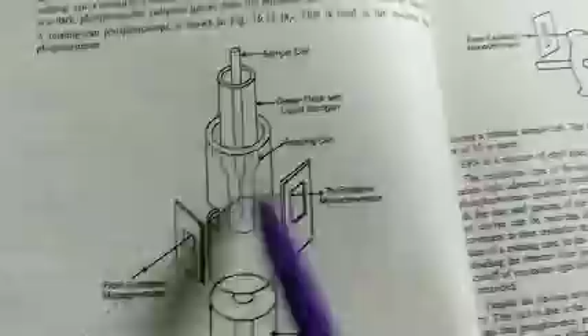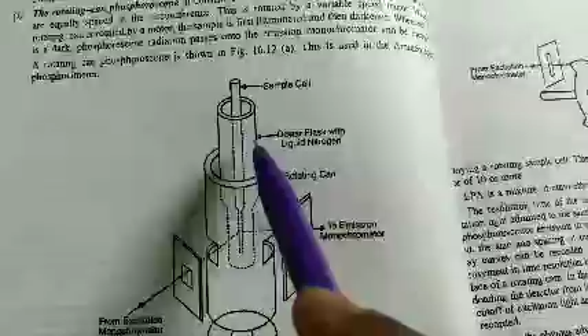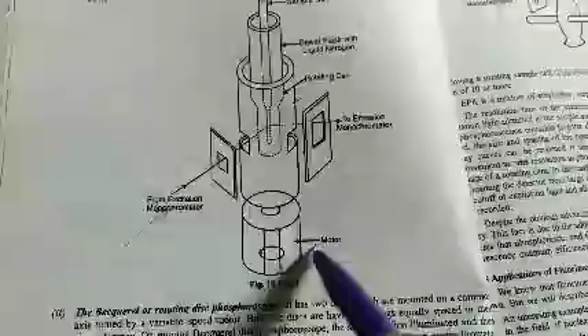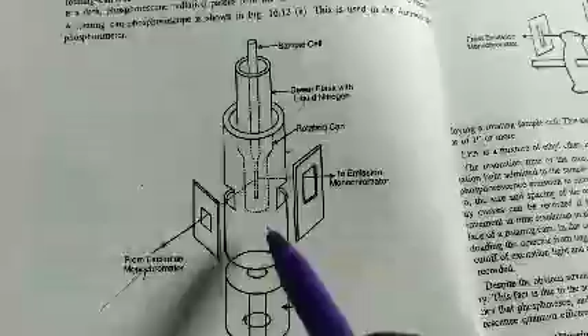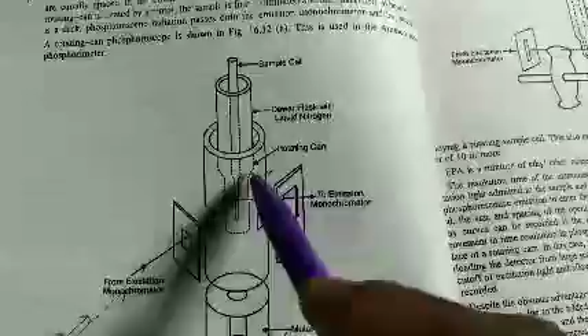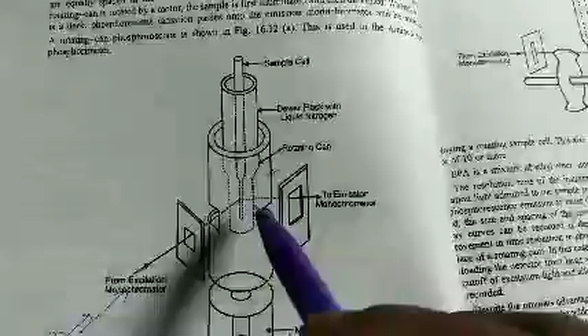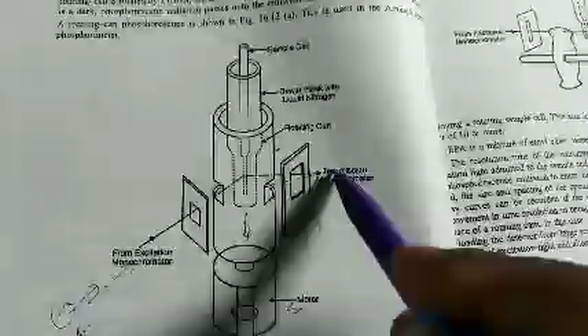In the rotating can phosphorimeter, the light source comes in, and the sample is kept in a Dewar flask. The Dewar flask is filled with liquid nitrogen, and this is the rotating can. The rotating can is attached to a motor, so there is an up and down movement. Here is the UV source of light, and the emission monochromator. When light comes from the lamp, the Dewar flask is in the upward direction, and after some time it comes downward and emits the radiation.